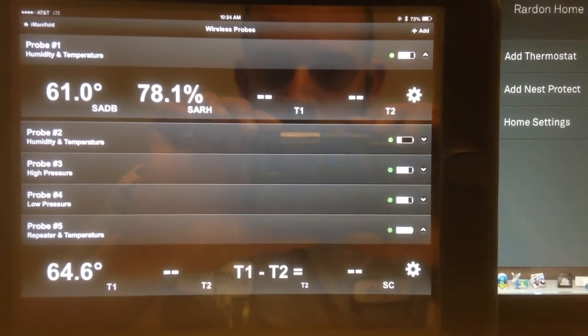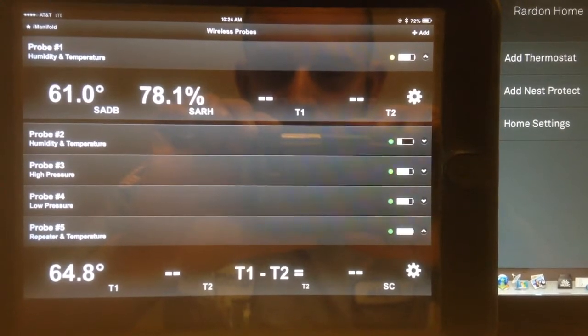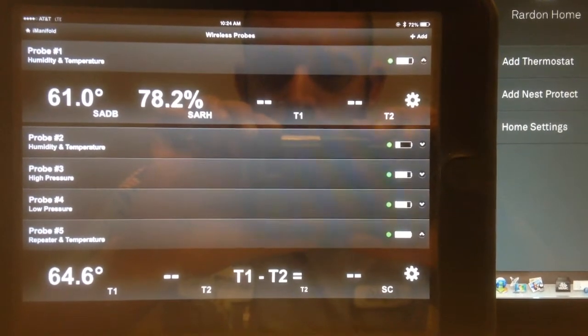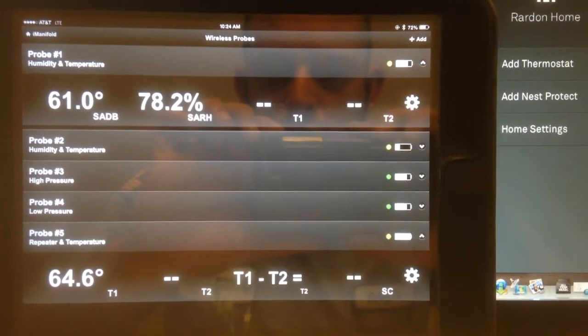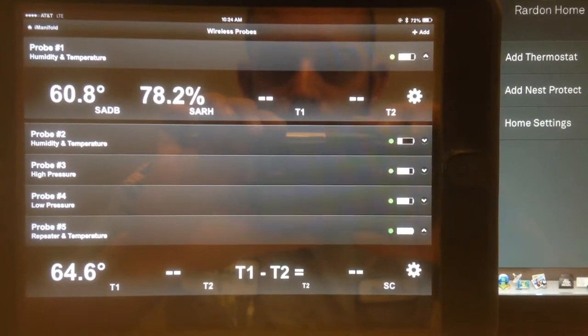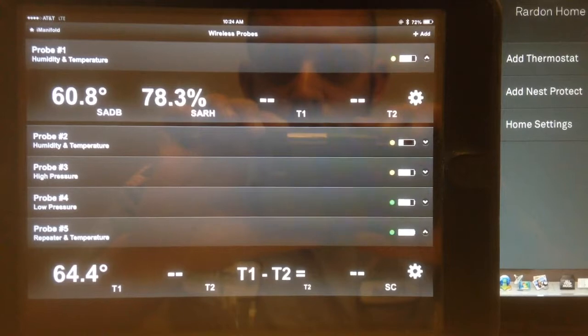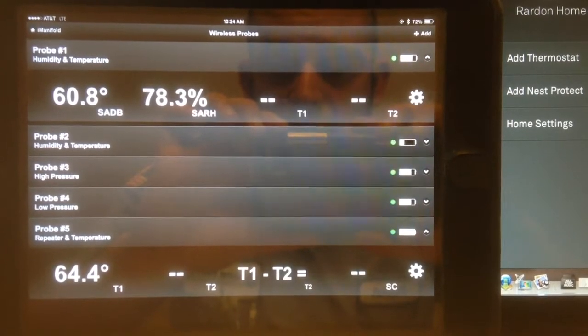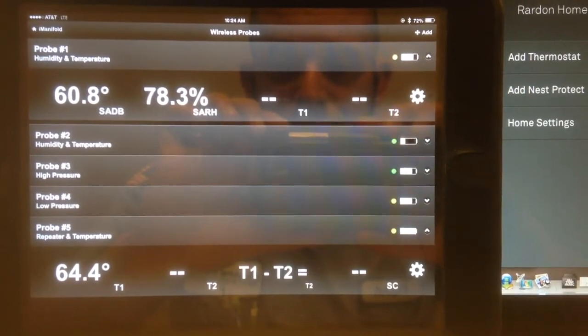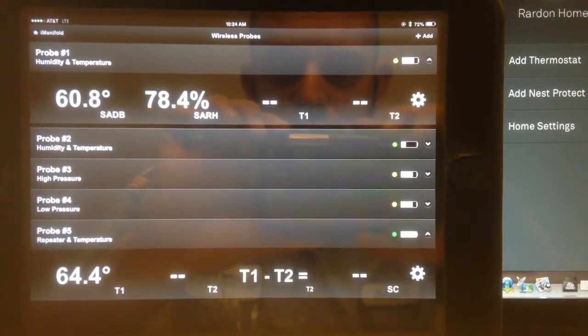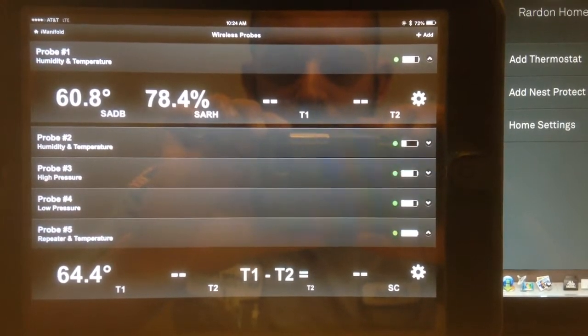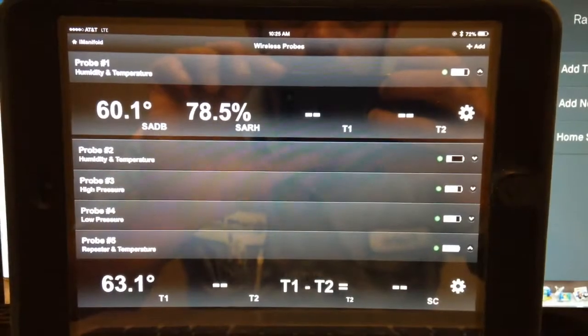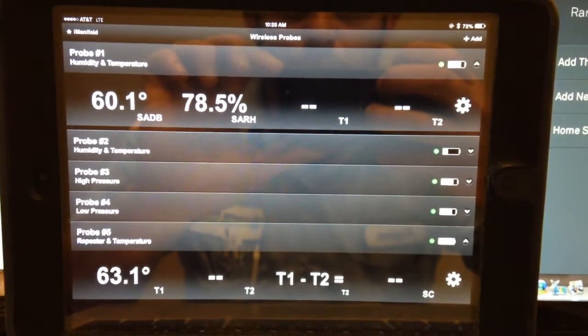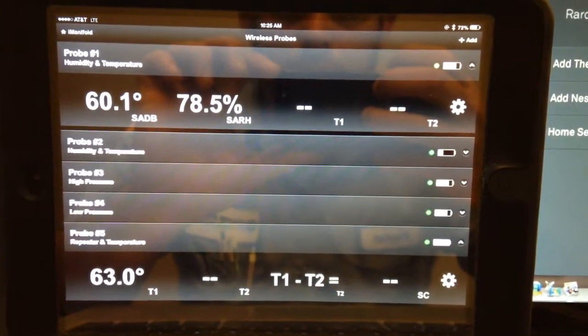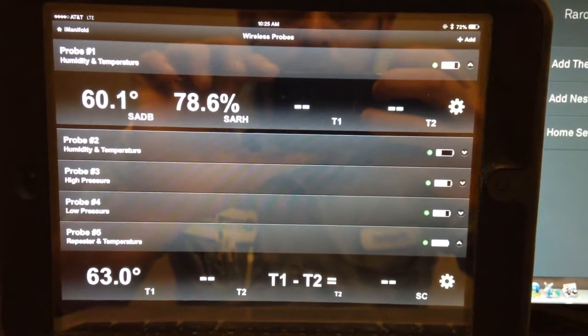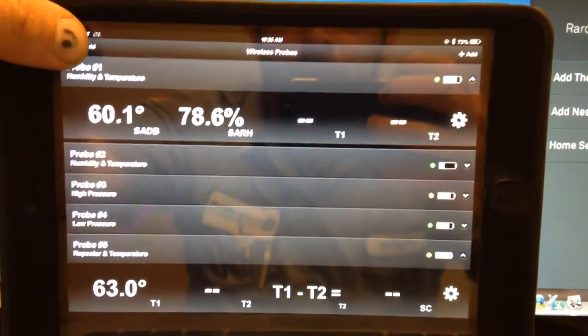So not necessarily something that is a specific tool, but it shows you how you could prove whether you're losing temperature across the ducting or whatever. You could prove that the insulation value is not exactly that great. Now, it may adjust over time. So it looks like the delta T between the distribution box and the register is getting a little bit closer.